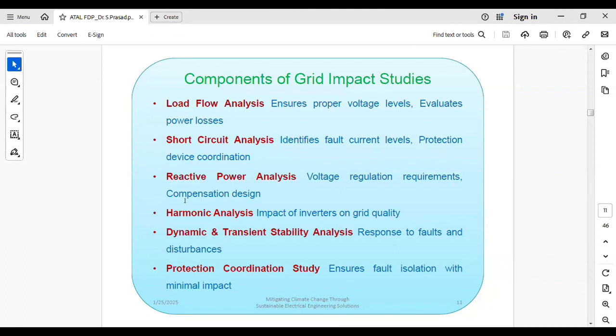during short circuit analysis. Then reactive power analysis, one of the most important tasks performed by the consultant. That means, whenever you are generating electrical power through PV generators and injecting it to the grid bus at the interconnection point, in order to maintain 0.95 power factor lagging and leading at the point of interconnection, how much reactive power needs to be injected, how much capacity of a capacitor bank or STATCOM or SVC should be connected at the PV end, so that the power factor can be maintained at the POI.